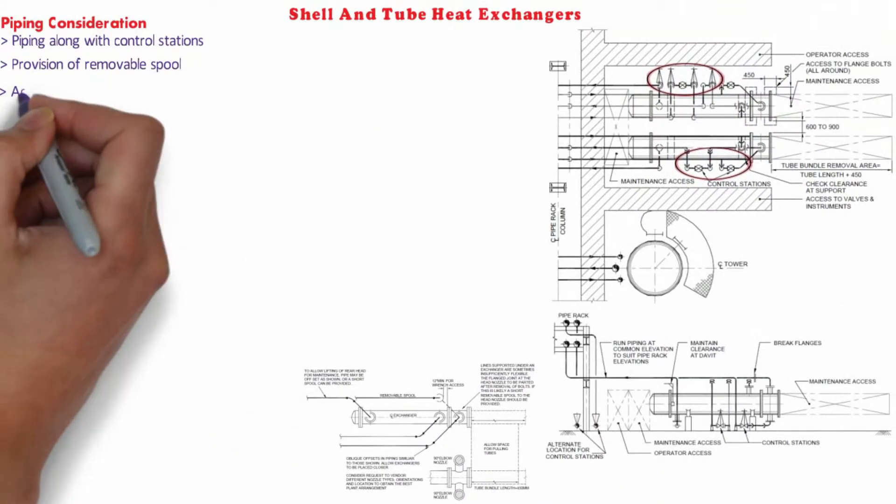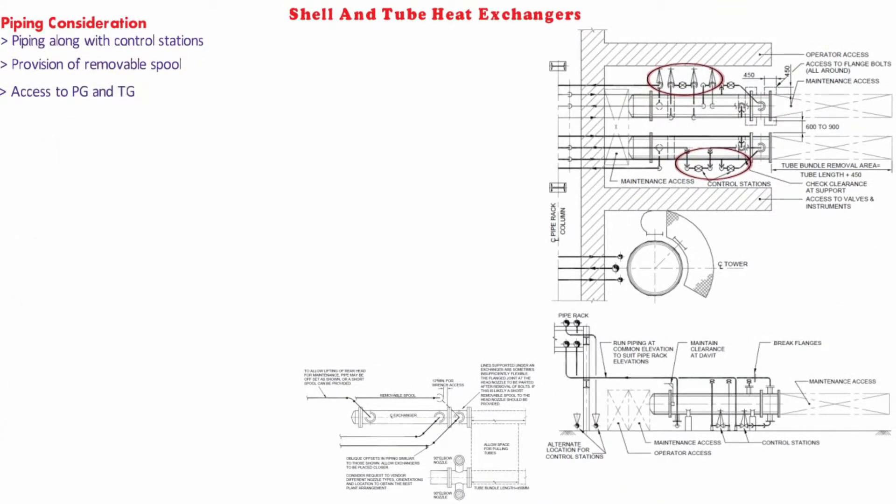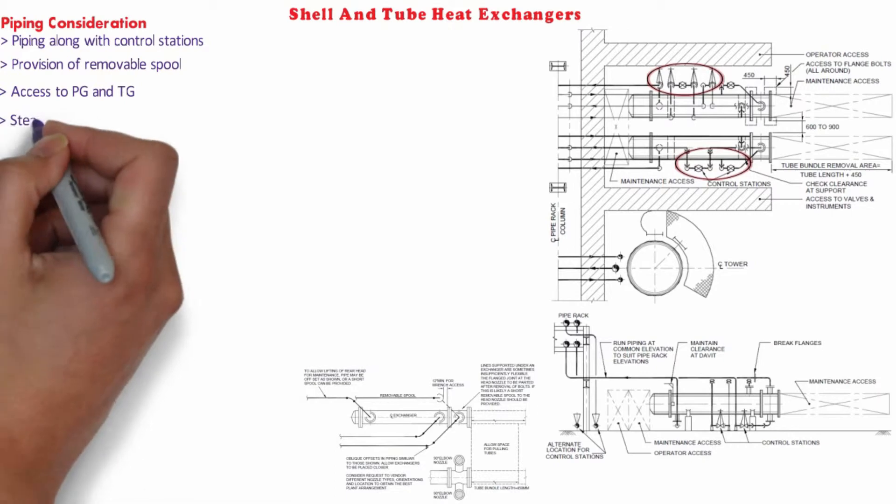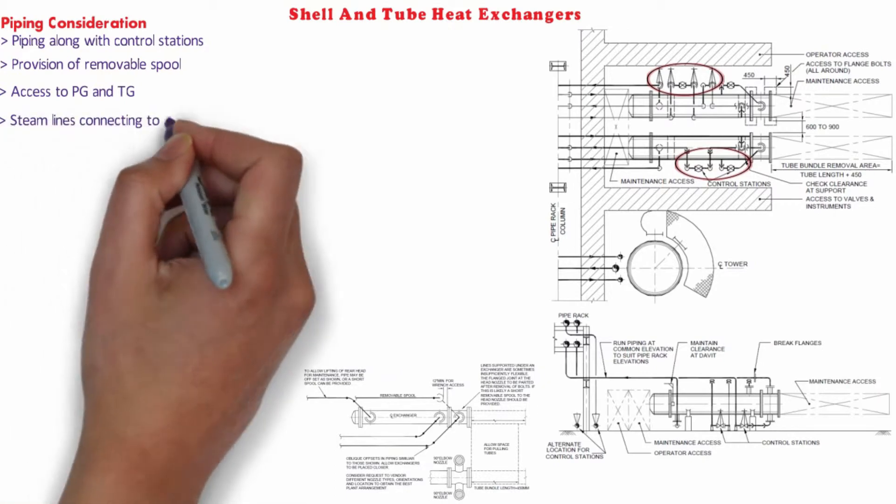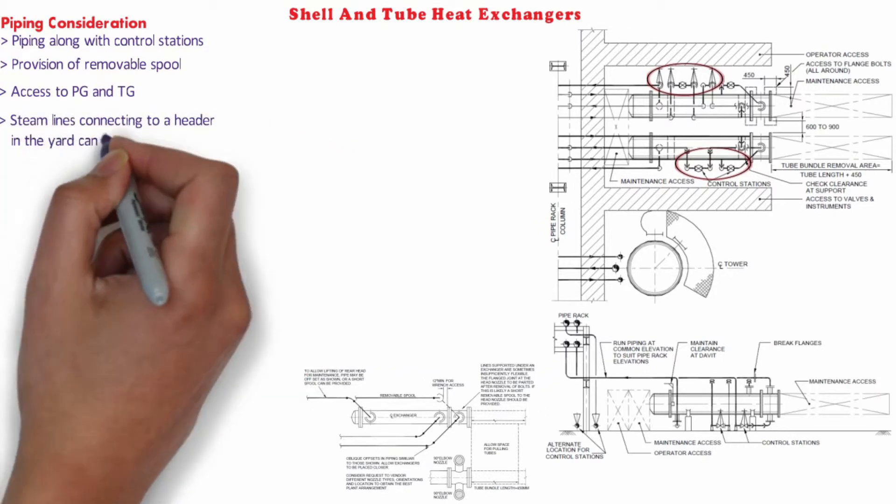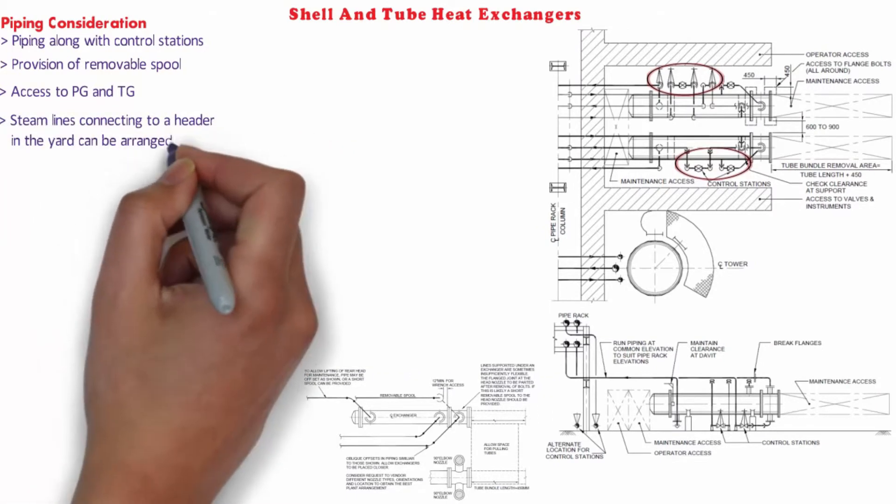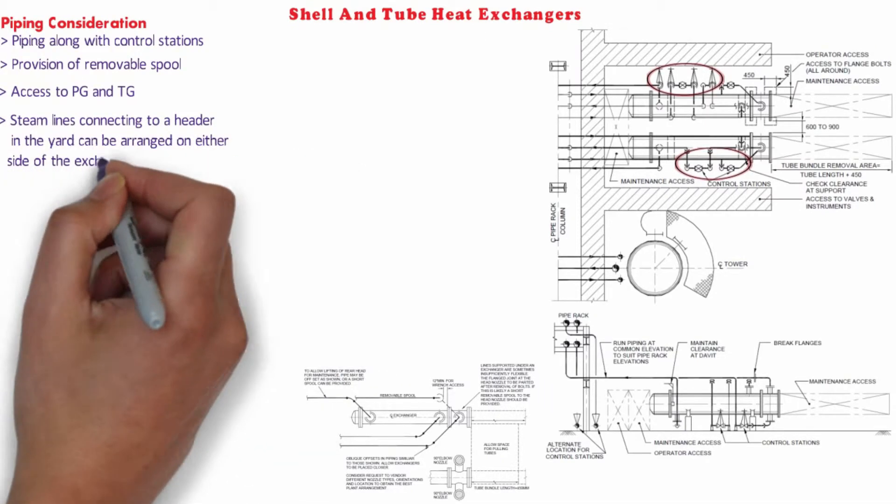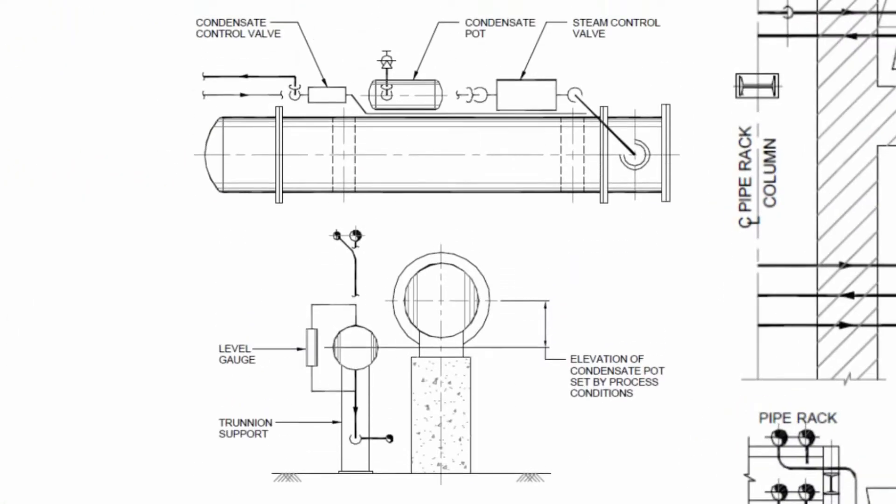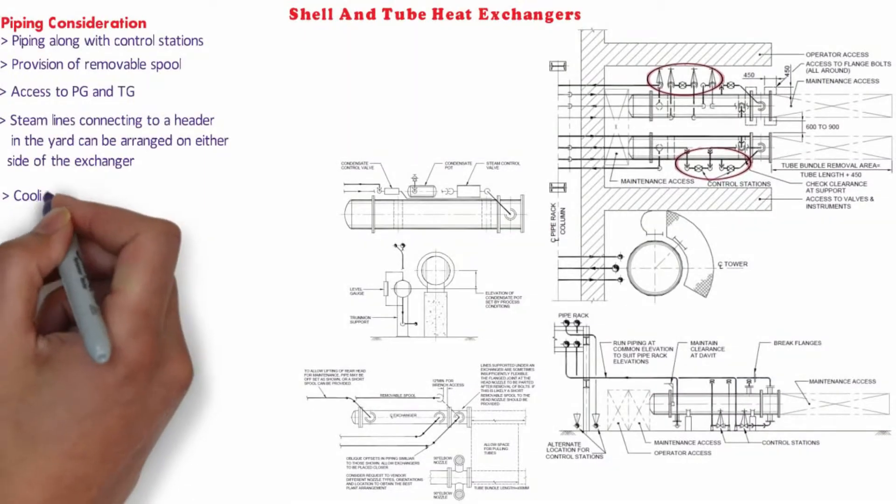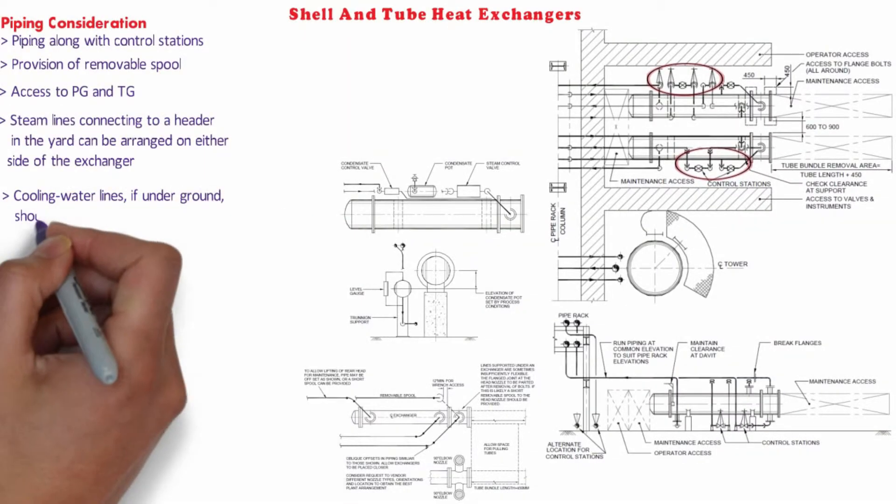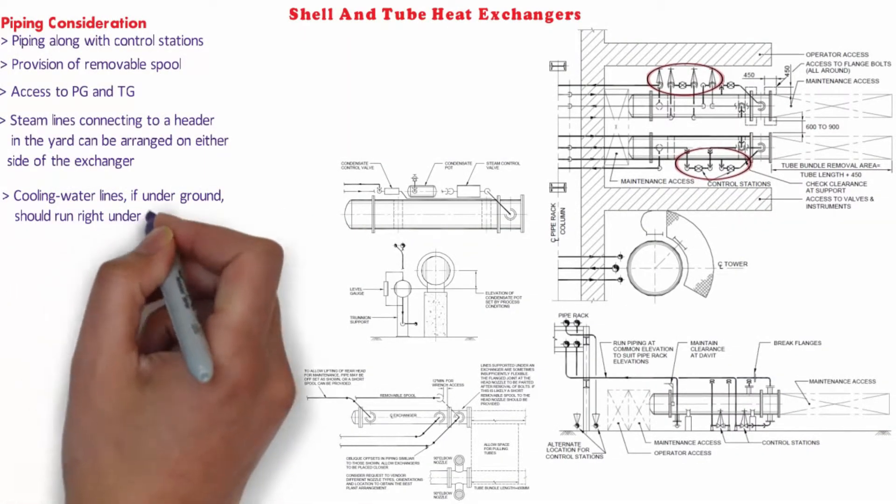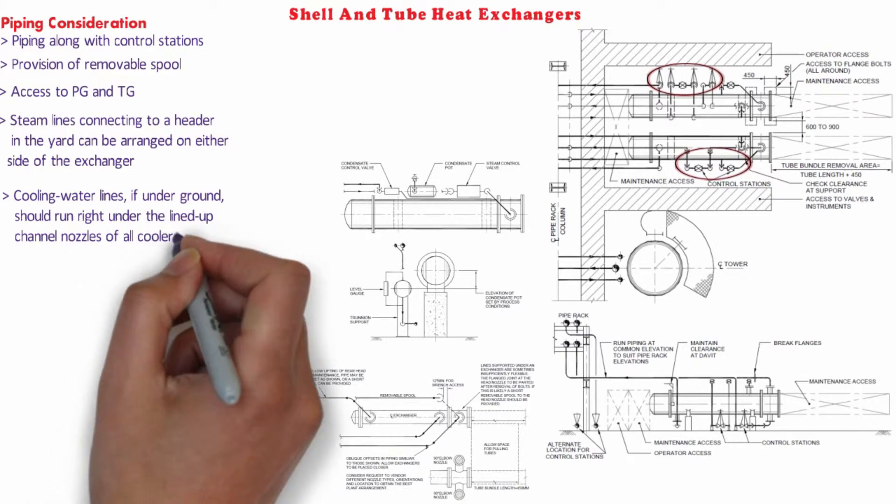Locally mounted pressure and temperature indicators on exchanger nozzles on the shell or channel lines should be visible from the same grade or access platform. The steam lines connected to a header in the yard can be arranged on either side of the exchanger center line without increasing the pipe length. Cooling water lines if underground should run right under the lined up channel nozzles of all coolers.